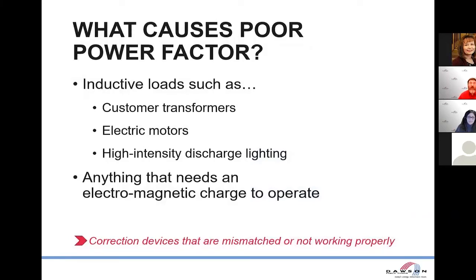So what causes poor power factor? Anything that is an inductive load causes your power factor to decrease. Some common examples: obviously electric motors is the big one. That is the number one cause of a reduced power factor.